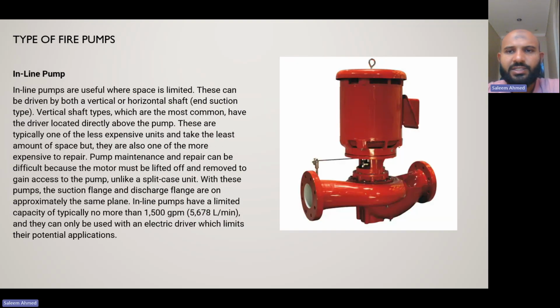Inline pumps are designed for space-saving installation in a fire protection system, typically in a building with limited room for larger pumps. This can be driven in both vertical and horizontal orientations, and most commonly we can see that the driver is located directly above the pump.